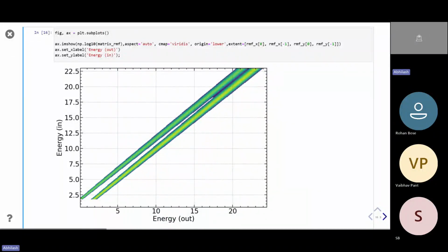So E minus that 1.74 energy makes another peak there. What you are essentially measuring is E minus 1.74. If that photon goes out, the amount of charge measured by the detector is E minus 1.74. So there is a peak which is called the escape peak. The difference between the energy of the main peak and the escape peak is always constant, which is equivalent to silicon K alpha.